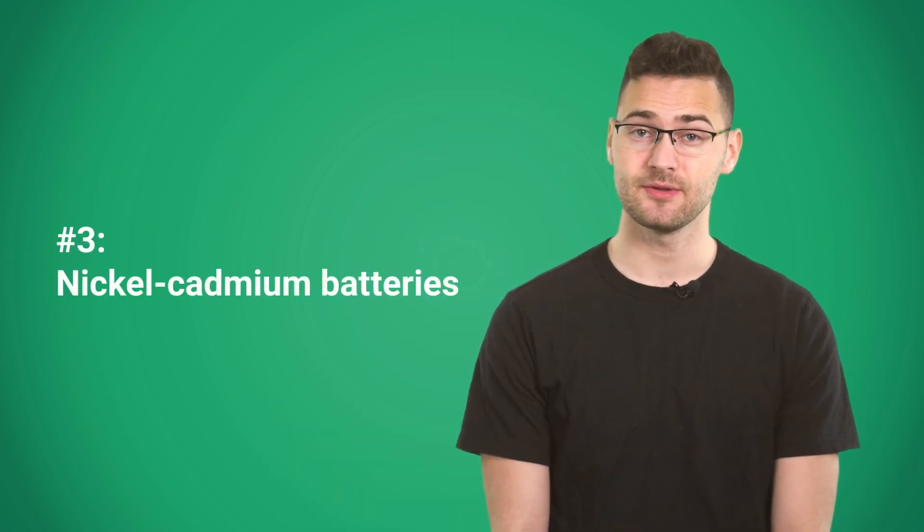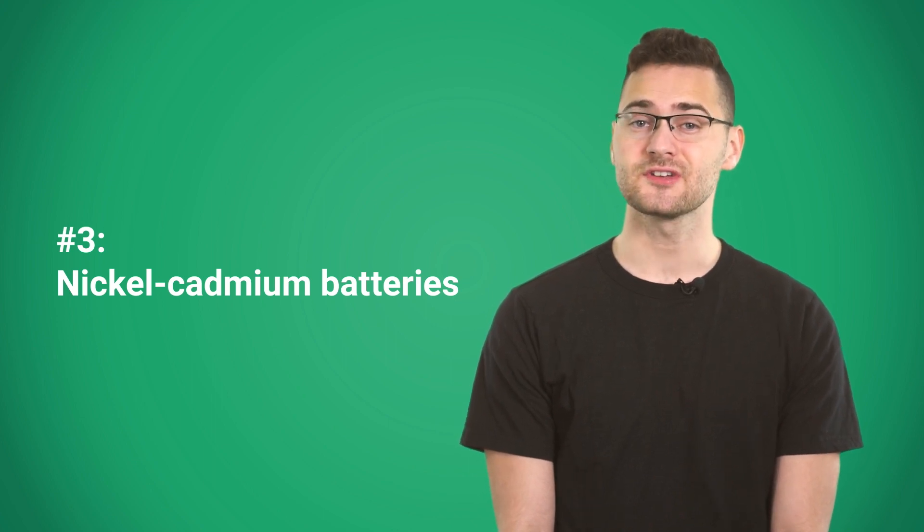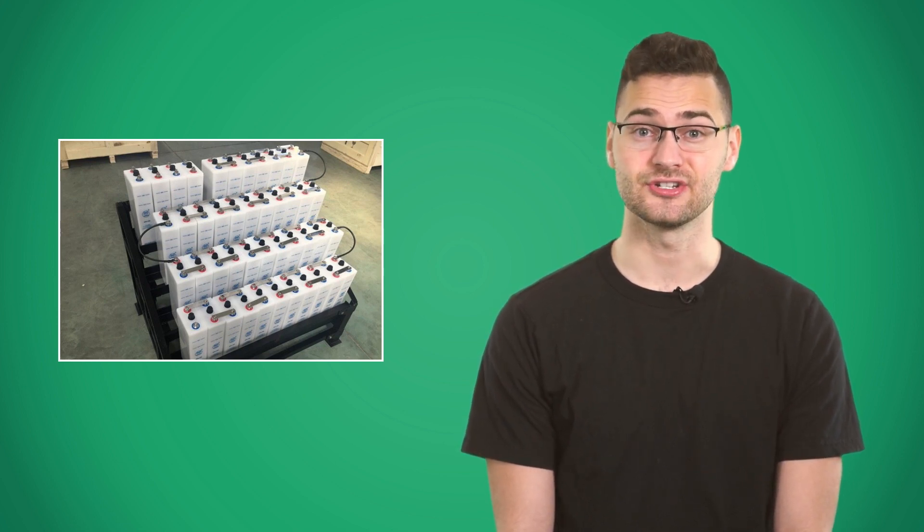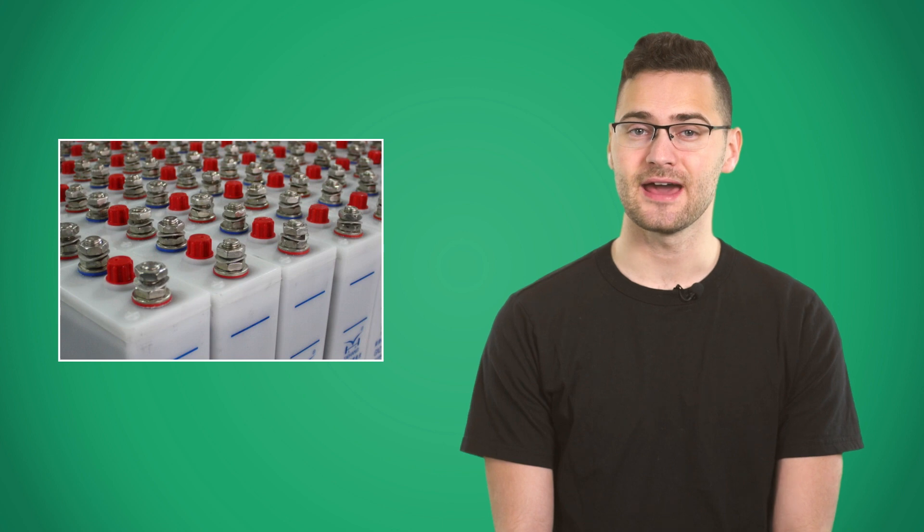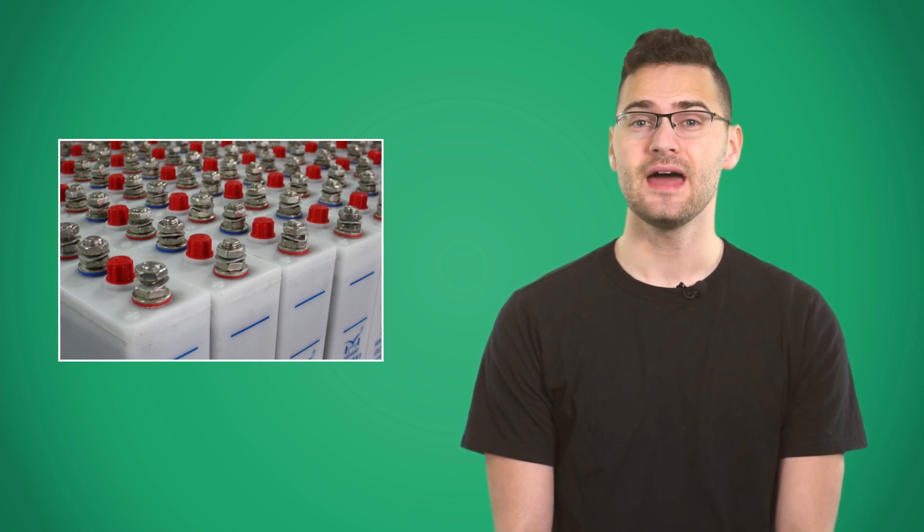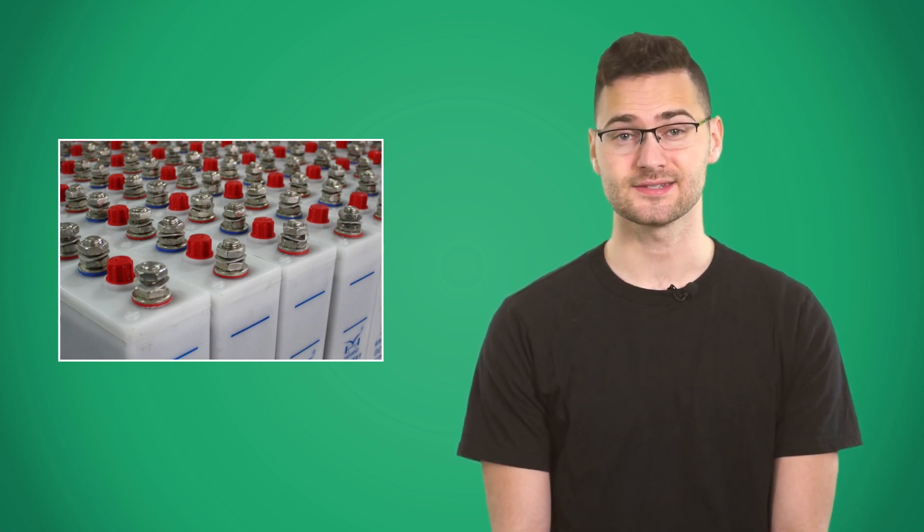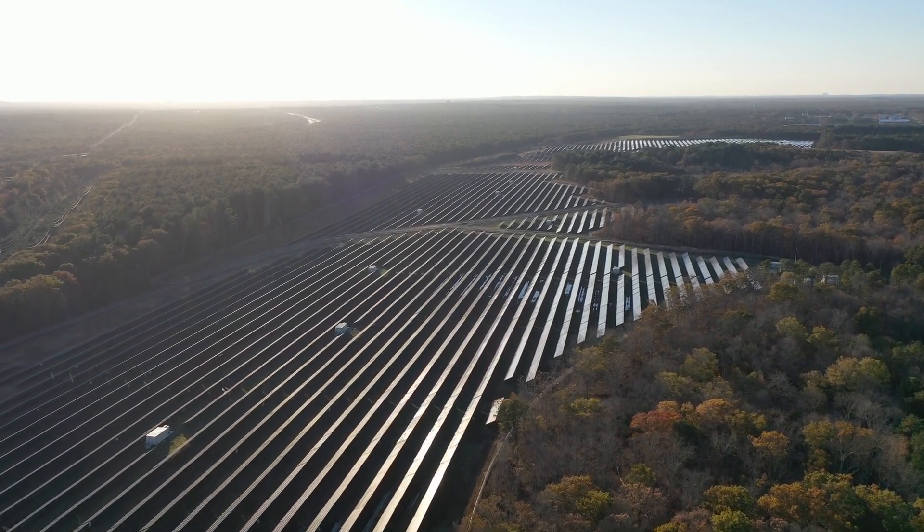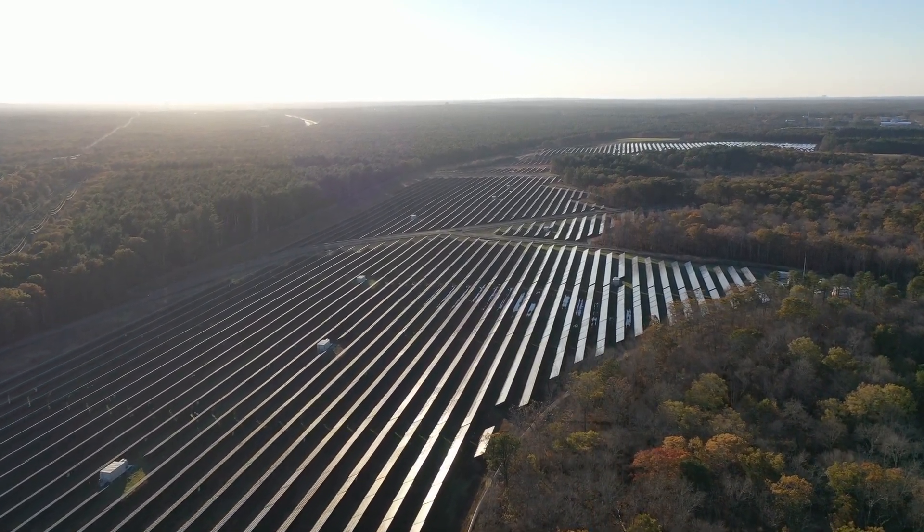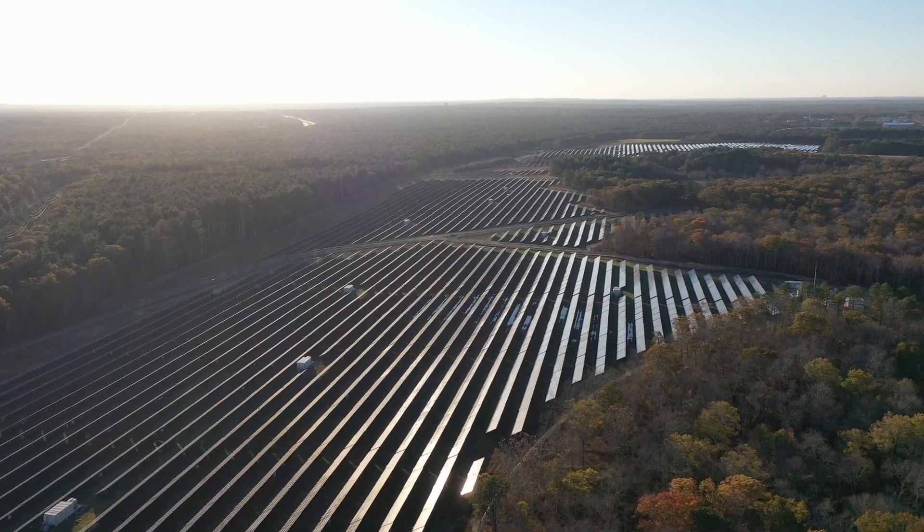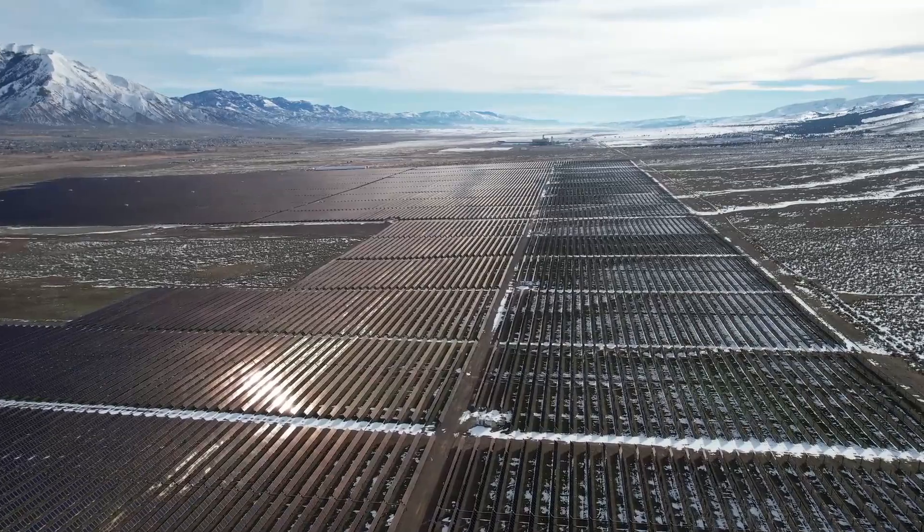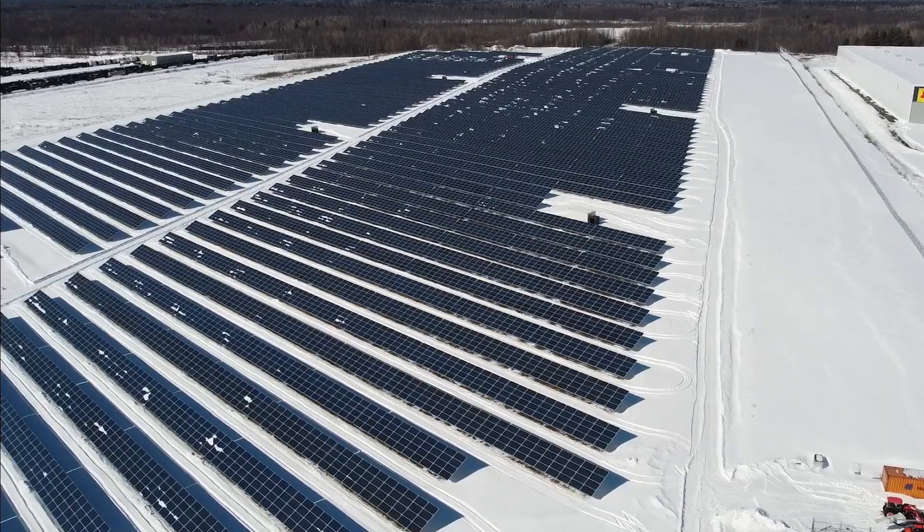The third type is nickel cadmium batteries. They are robust and withstand extreme temperatures well. They are more expensive than lead acid batteries, but they last longer and have a higher energy capacity. Lithium ion batteries are still smaller though, and these two types are comparable in cost. You often see nickel cadmium batteries in large solar projects where you deal with megawatts of power, and you often need to discharge a battery quickly. They are also a go-to choice in harsh conditions. They are probably the best choice for a really cold place.